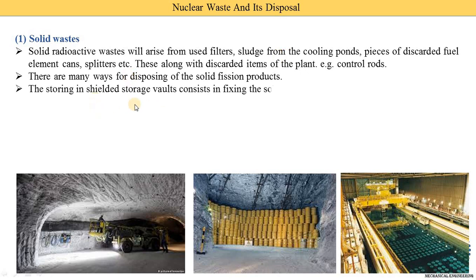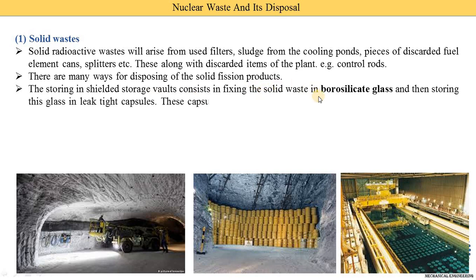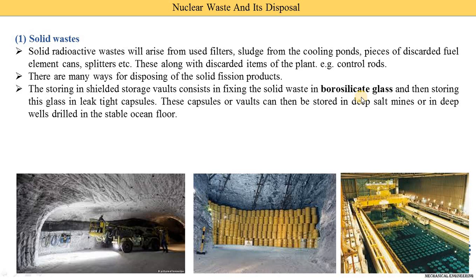There are many ways for disposing of solid fission products. The first method is storing in shielded storage vaults, which consists of fixing the solid waste in borosilicate glass. This borosilicate glass is then put in liquid-tight capsules. These capsules or vaults can be stored in deep salt mines or in deep-well drills in the stable ocean floor — meaning we drill a hole in the ocean floor and place the capsule there.